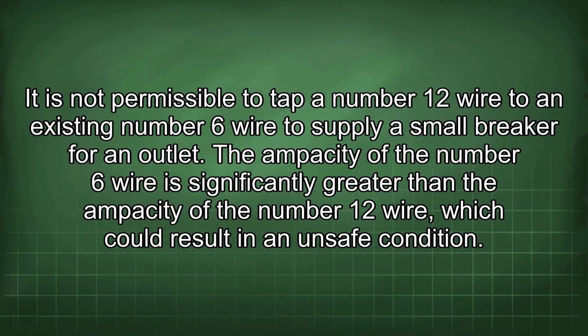It is not permissible to tap a number 12 wire to an existing number 6 wire to supply a small breaker for an outlet. The ampacity of the number 6 wire is significantly greater than the ampacity of the number 12 wire, which could result in an unsafe condition.